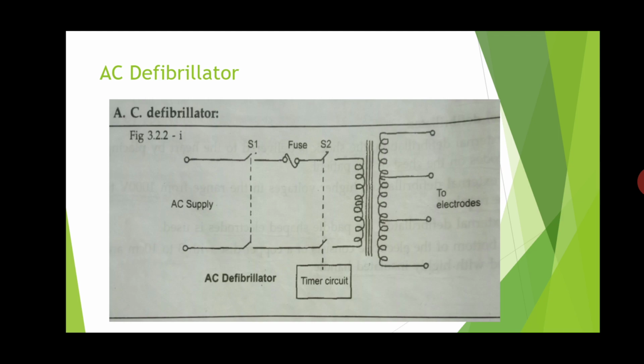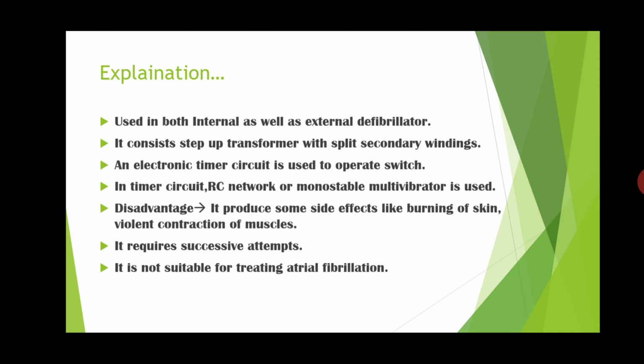The disadvantages of the AC defibrillator. The first disadvantage: the AC defibrillator will produce some undesirable side effects like violent contraction of the muscle and burning of the skin under the electrodes. Second disadvantage: if it is used to correct ventricular fibrillation, then successive attempts are required. Third disadvantage: the AC defibrillator is not suitable for treating atrial fibrillation.